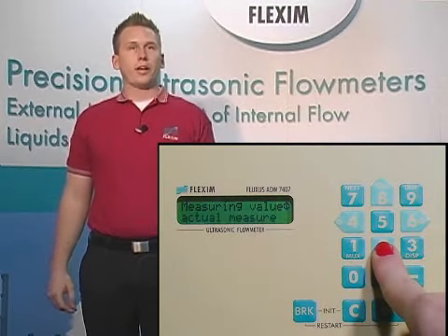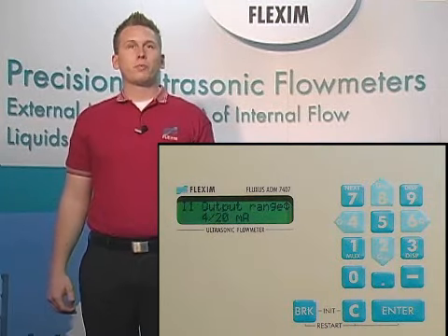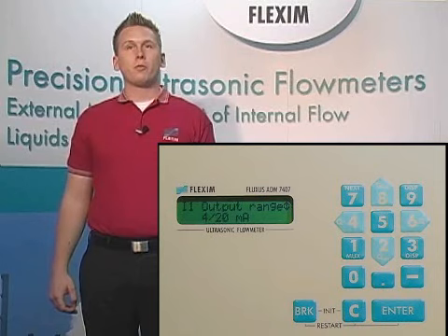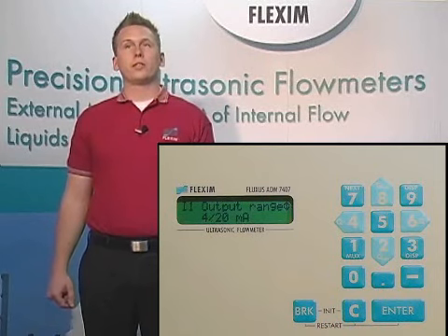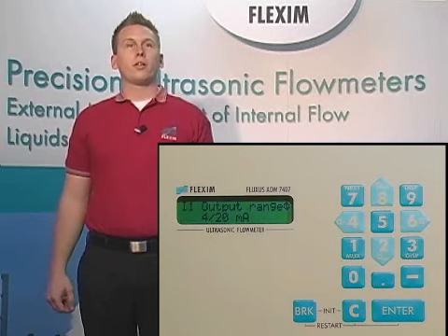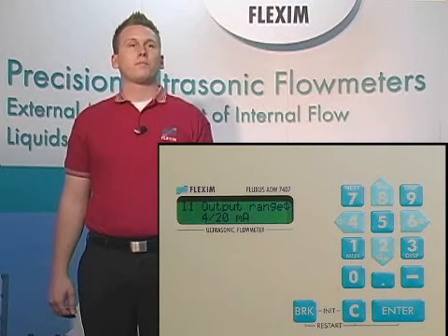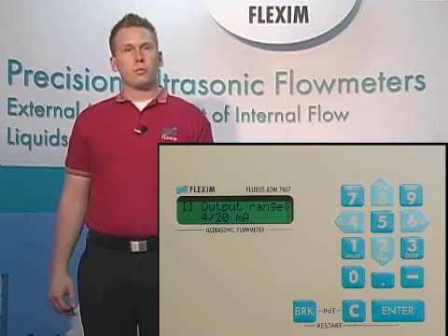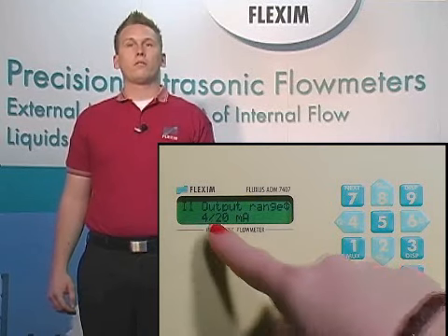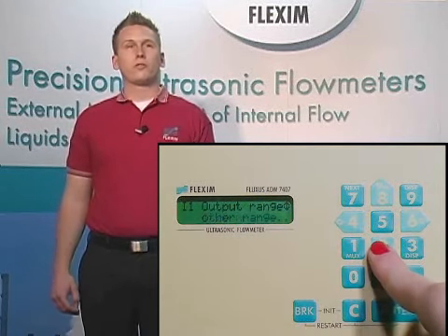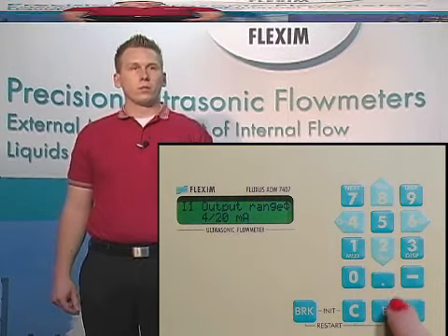Next, we choose actual measure. This will let us put out as a 4 to 20 whatever we set as our main output for the LCD. This is the option that generally makes the most sense for our customers. Now we can choose the type of current output to use, 0 to 20, 4 to 20, or other values. Of course, we're going to choose 4 to 20 and hit enter.